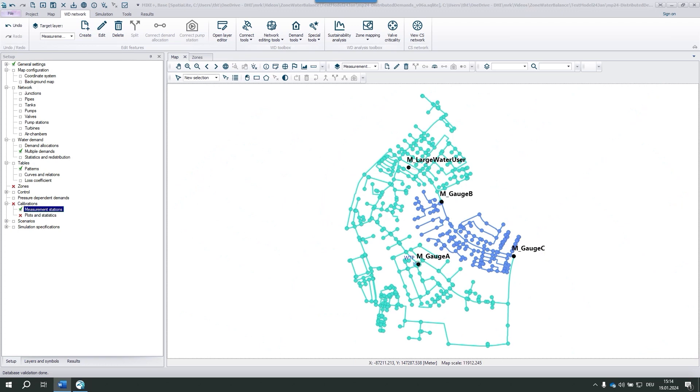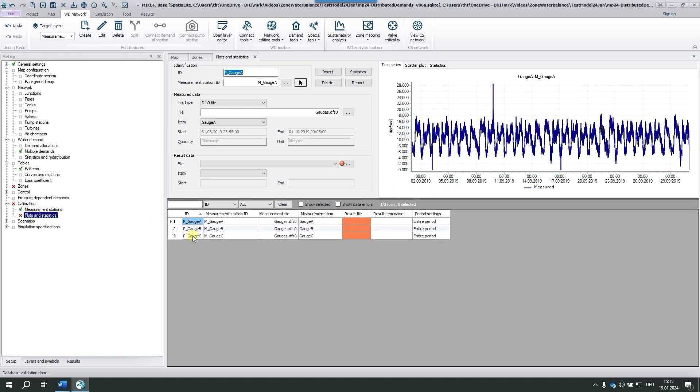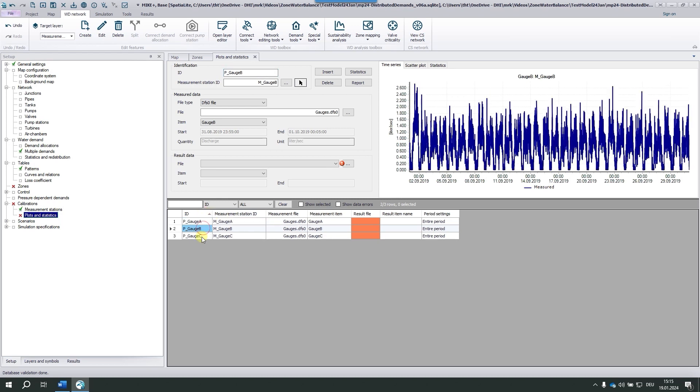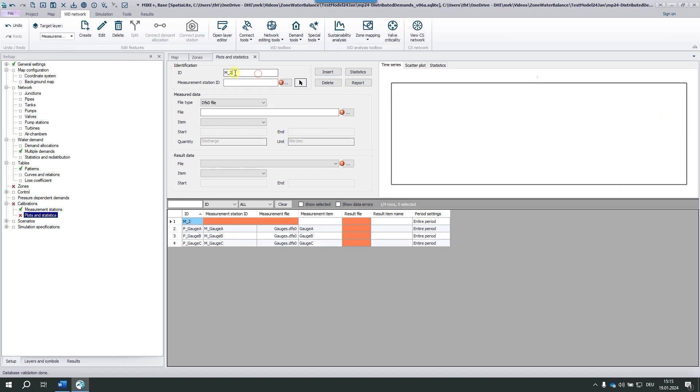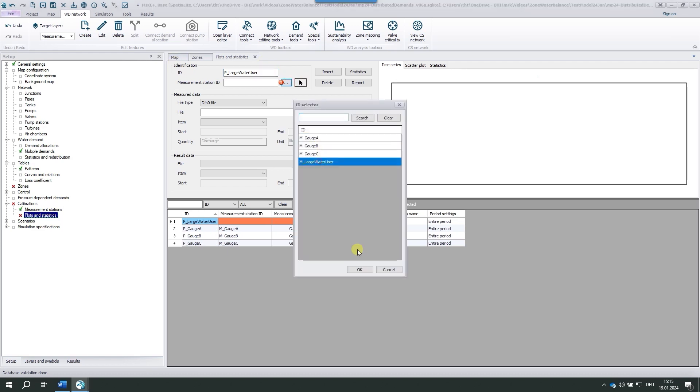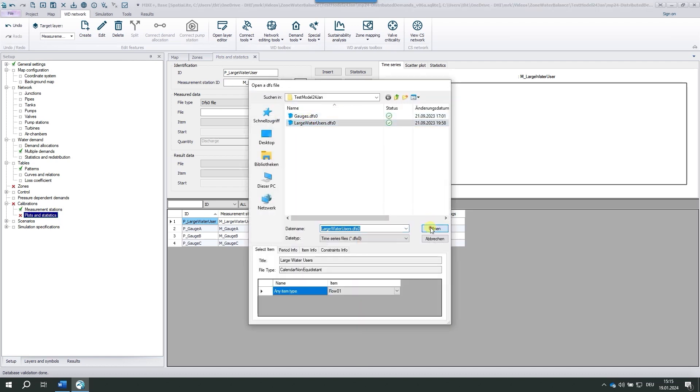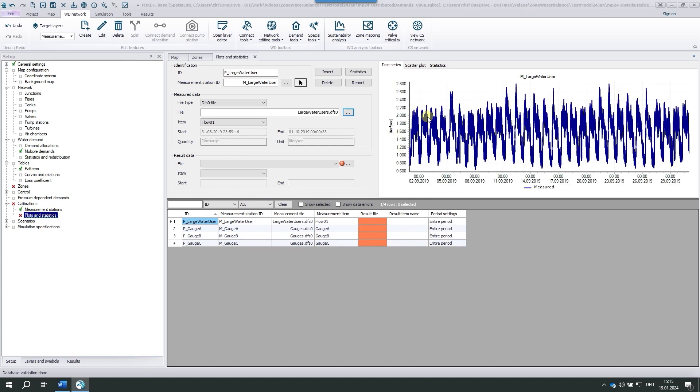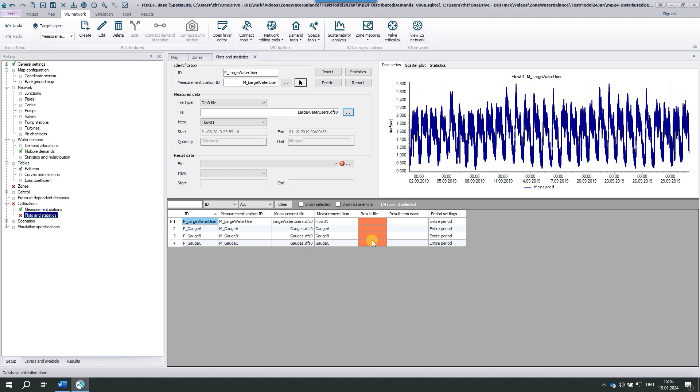Each measurement station may have several associated plots. That's why we need an additional editor. There are the three gauges with their time series. We insert a new plot: large water user. We pick the measurement station and we choose the time series file. Here's the time series which we've seen already. The editor complains about a missing result file, but we would need result files only if we calibrated the model, which we won't. So we ignore this error and indeed the zone water balance is not affected. Now we have all four measurements in our model.